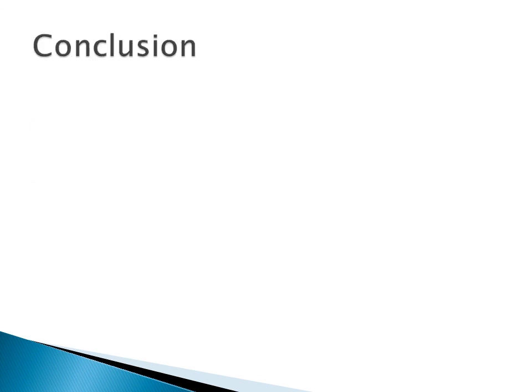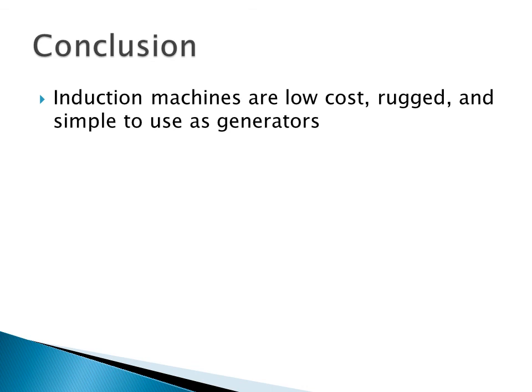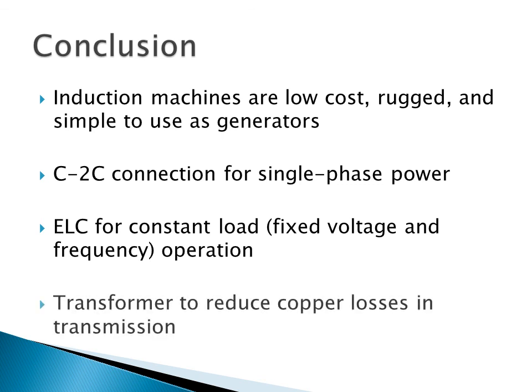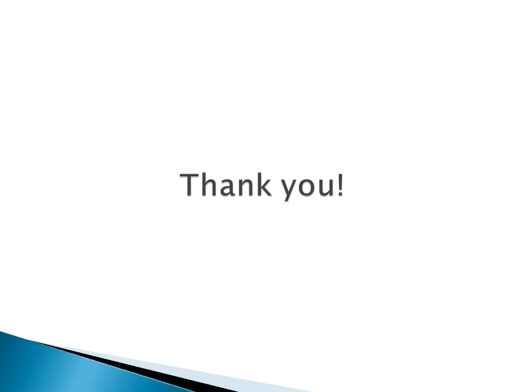To conclude, we have presented that the induction motors are low-cost, rugged, and very simple to use as generators. They can be found worldwide, and they are robust and well-suited for the application. We can get single-phase power from a three-phase machine by proper selection of a capacitor bank, and proper connection in the C2C configuration. We can use a basic electronic load controller to operate a constant load to fix the output voltage and frequency. And we can use a transformer to reduce copper losses in transmission over longer distances. And that concludes the presentation. I'd like to thank you for your time, and if you have any comments or questions, please leave them below in the comment section.